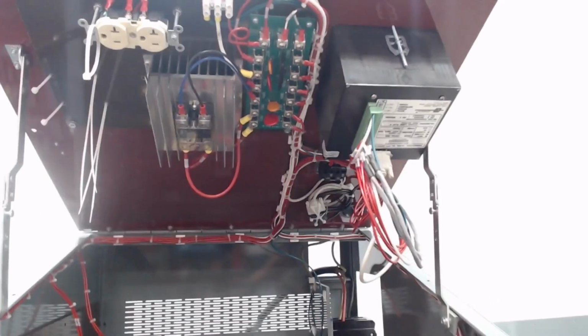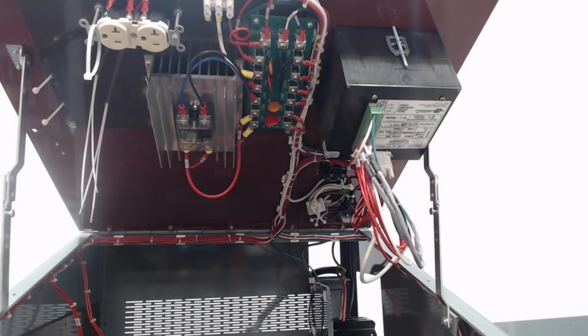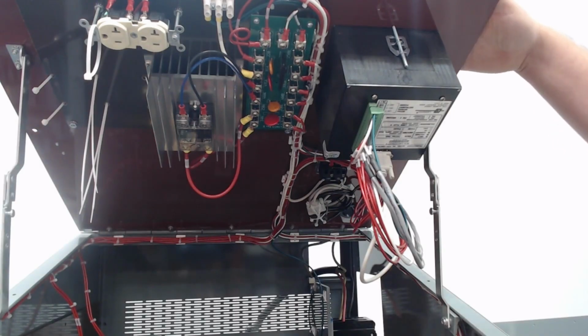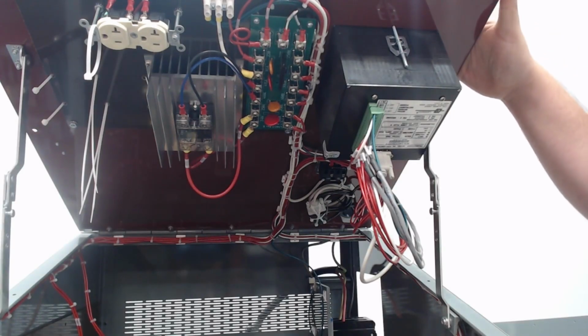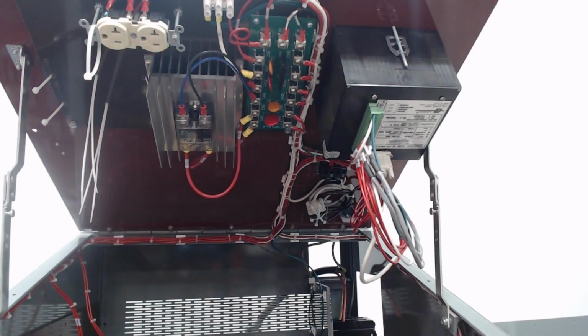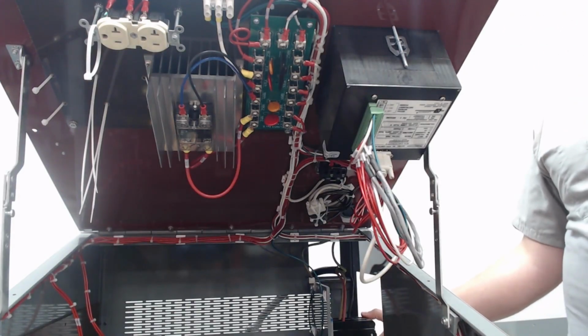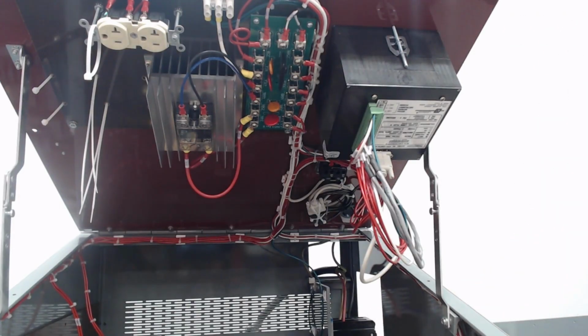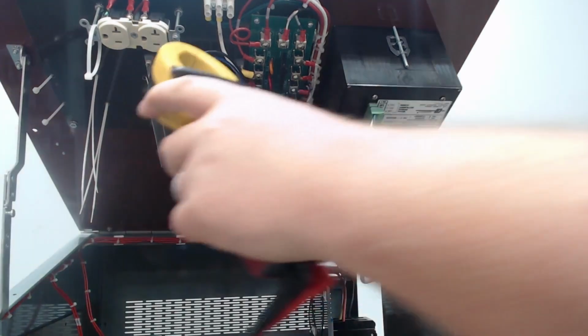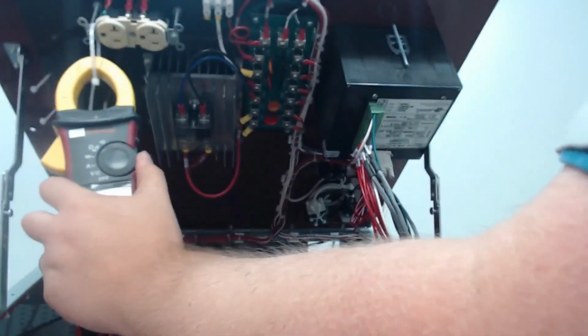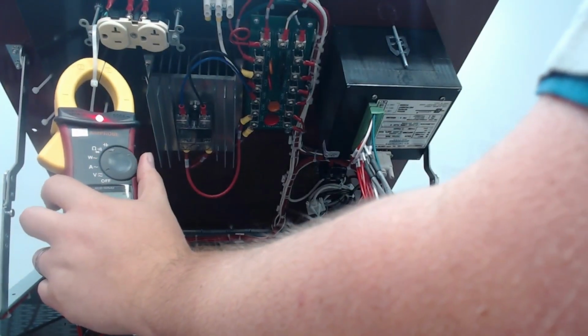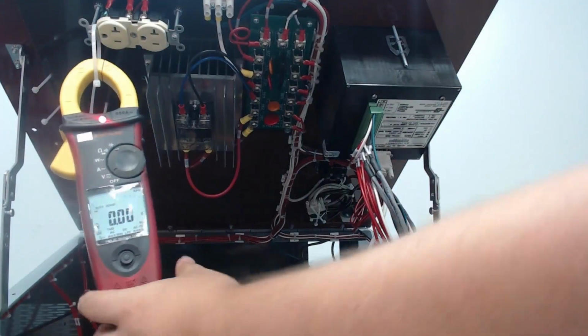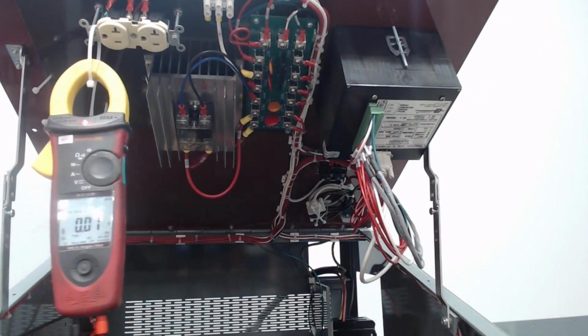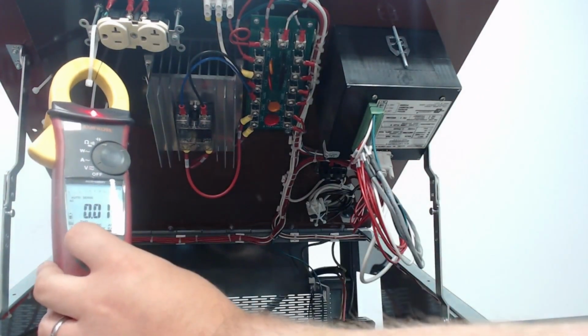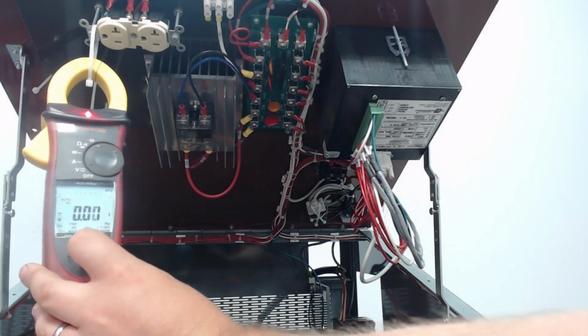So in this case, we're going to go ahead and turn this on, and I'm not going to be able to show you that meter. I'm just going to have to tell you what's going on, and we'll go off of that. So unit is now energized. We're operating our unit at 460 volts incoming. I have my multimeter here, and the first thing we're going to do is go to volts. We can see that? Good. Okay, volts.